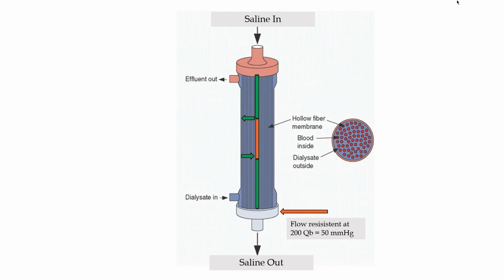So saline comes in. If that cap was not there to retain the pressure, the saline will take its least path of resistance. And it could be down, and you can have air locked in here and comes out of that fiber, and then re-emerges past that airlock and out your saline. If you have multiple fibers with that scenario, guess what happens when the blood comes in? Blood is so viscous that blood will force that airlock and liberate it into the venous segment. And obviously, with the 200 resistance of the venous end, the faster the blood flow, the greater the ultrafiltration. And that's why they maintain that your blood flow has to be at that minimal speed so that you don't have air in your system when the blood comes in.